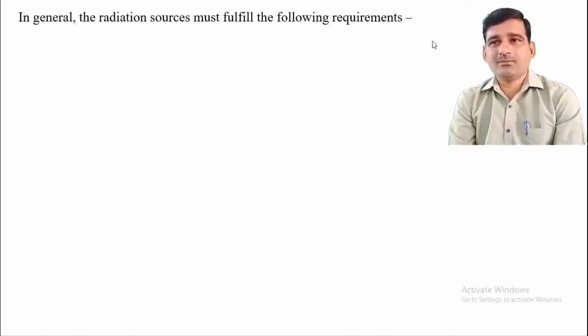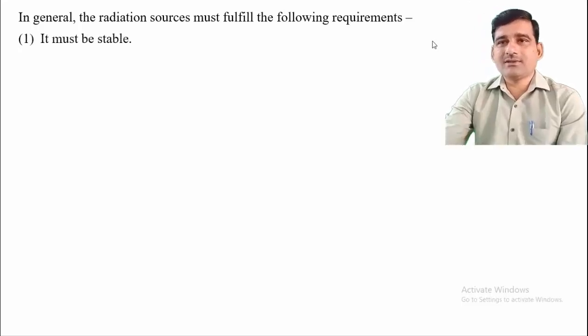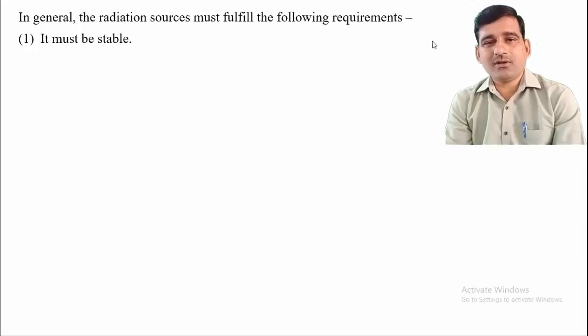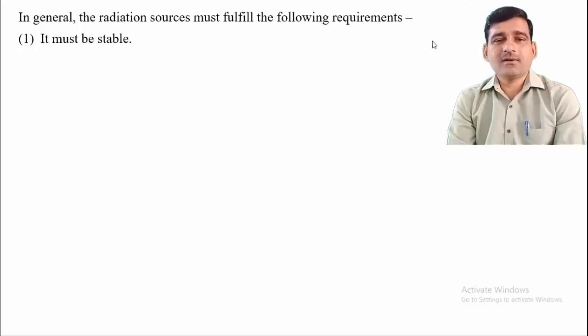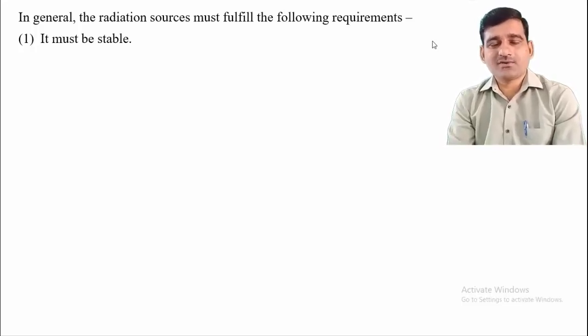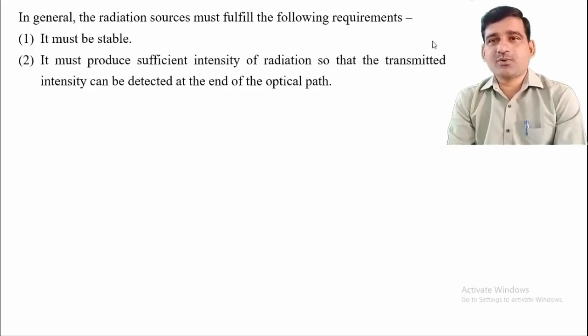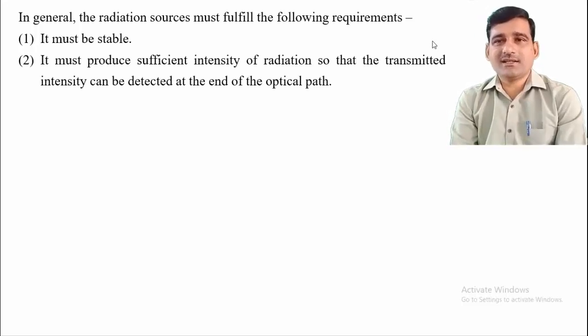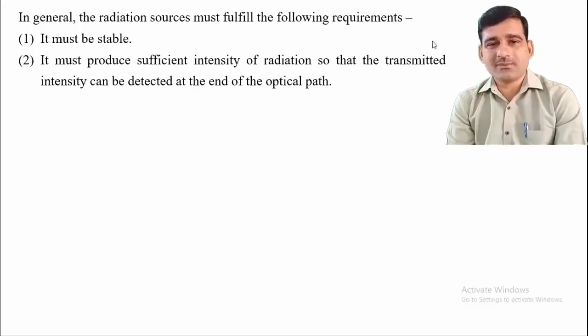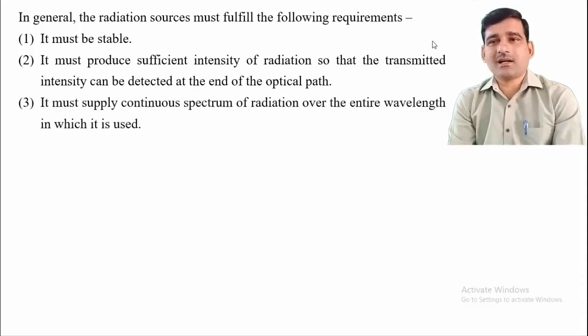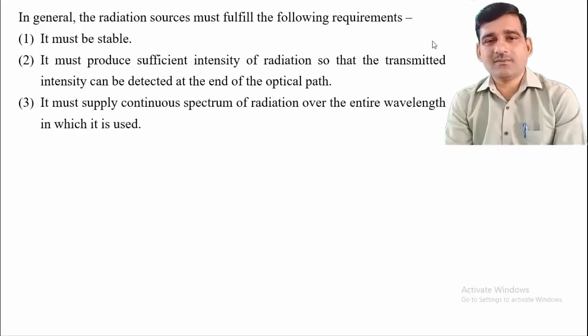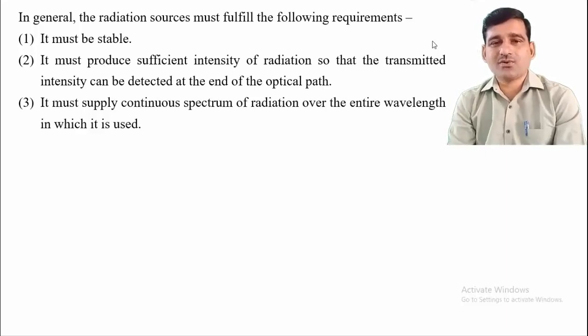In general, the radiation source must fulfill some requirements when used in ultraviolet and visible spectrophotometry. First, it must be stable to provide a continuous spectrum. Second, it must produce sufficient intensity of radiation so that the transmitted intensity can be detected at the end of the optical path. Third, it must supply a continuous spectrum of radiation over the entire wavelength range in which it is used.